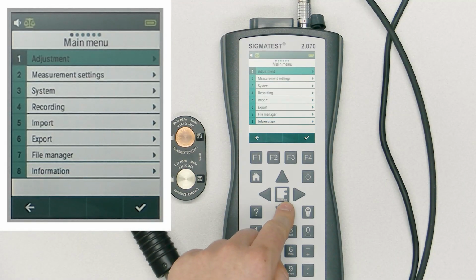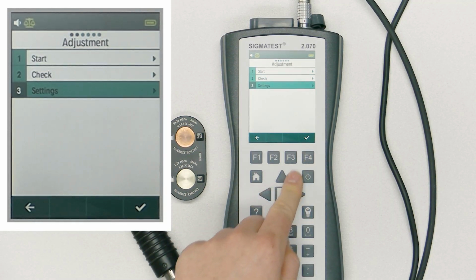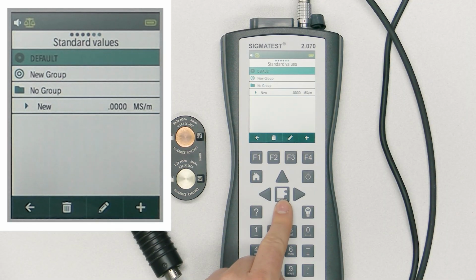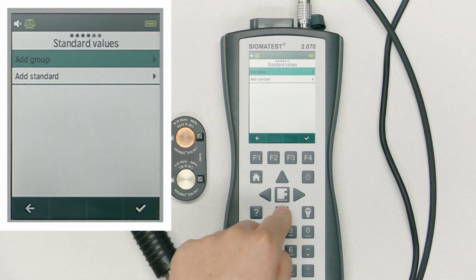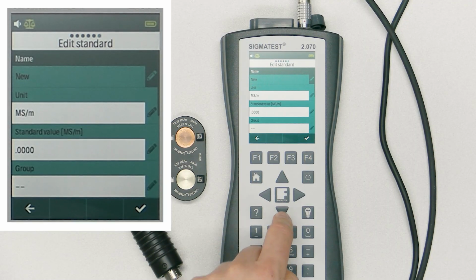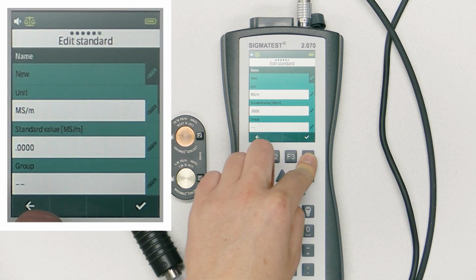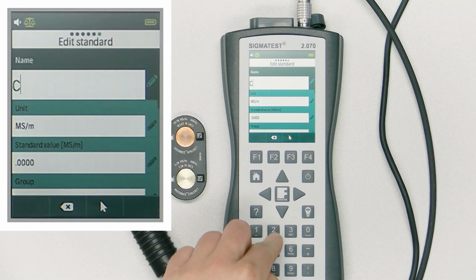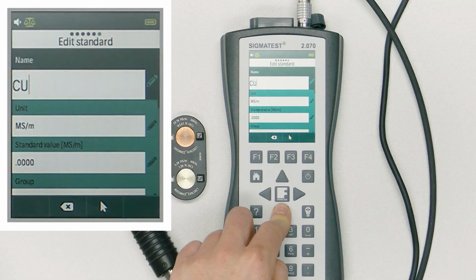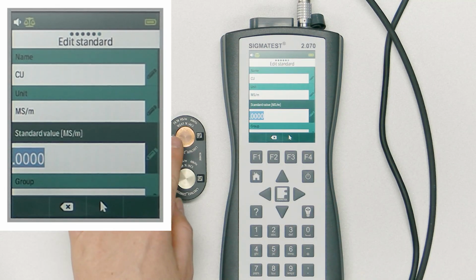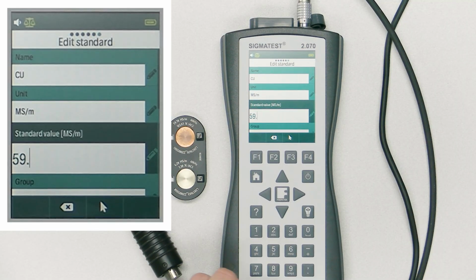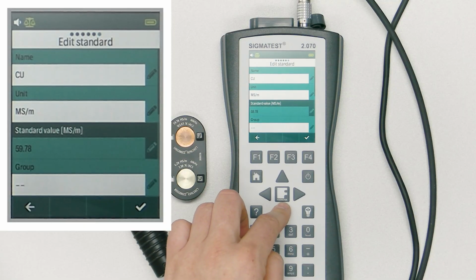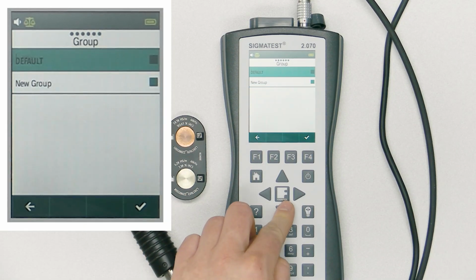To perform a new adjustment, the conductivities of the available calibration standards must first be entered into the system. I enter the calibration standard under the following path: Main menu, Adjustment, Settings, Standard value, plus, Add standard. First I enter the copper. I name it CU. It has a value of 59.78. And it shall go into the group default.